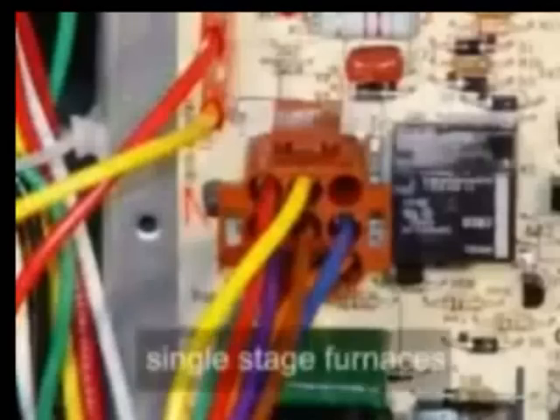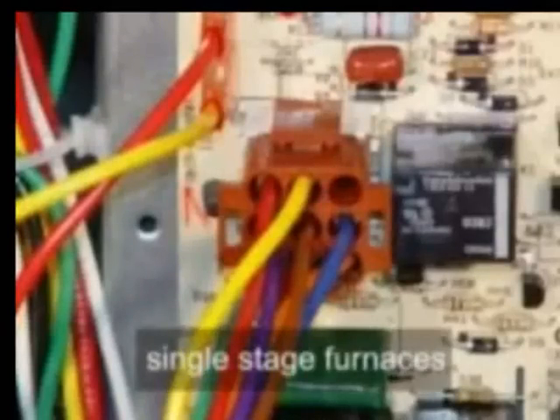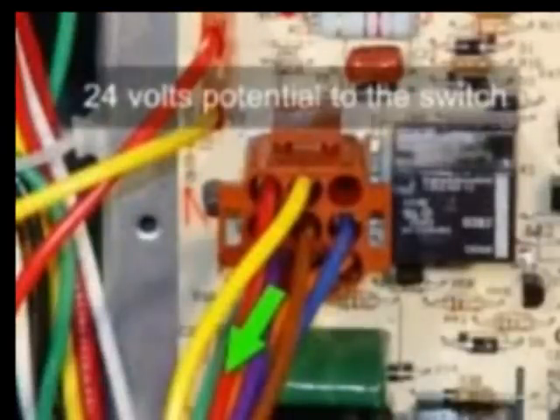The 9-pin plugs are for single-stage furnaces and the 12-pin plugs are for two-stage furnaces. The plugs have two pins that connect to the furnace limit devices. One pin sends 24 volts potential to the limit switches, and the other pin receives the 24-volt potential back to the IFC.